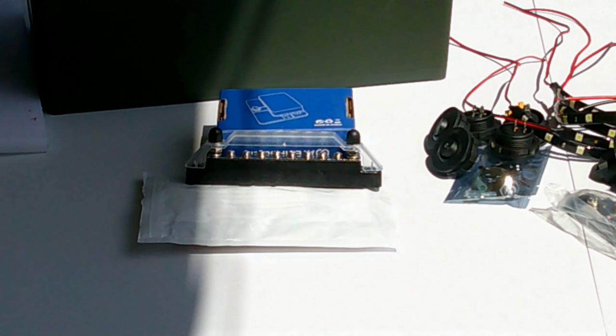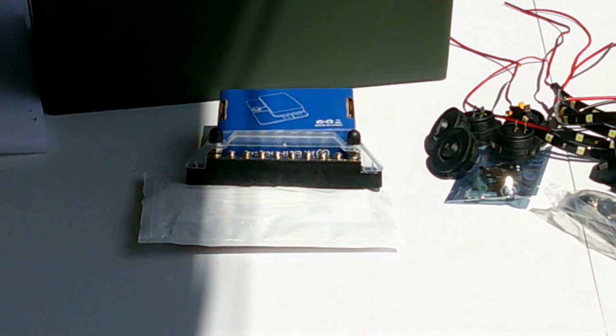The negative bus bar is rated for 150 amps DC. It has 10 contact points. The bar itself and the hardware are stainless steel. It has 2 M6 studs, one on each end, and 8 M4 machine screws for connection points. It comes with hardware for mounting, as well as ring terminals, both M6 and M4, to make connections, though I'll probably use some of my own. And that's it for the bus bar.